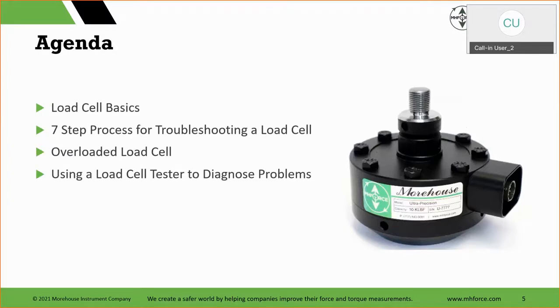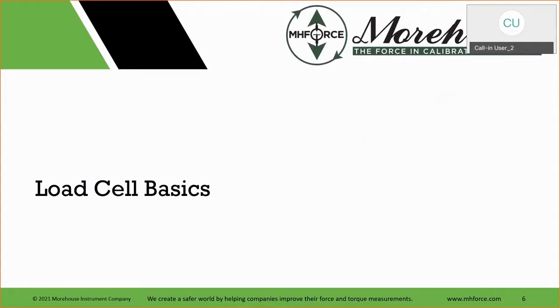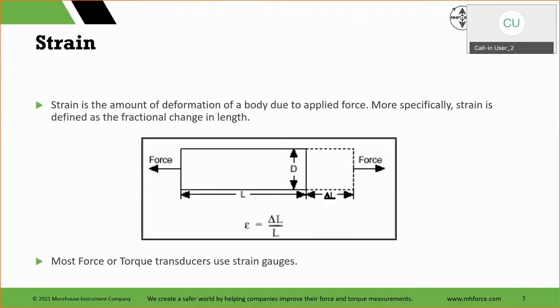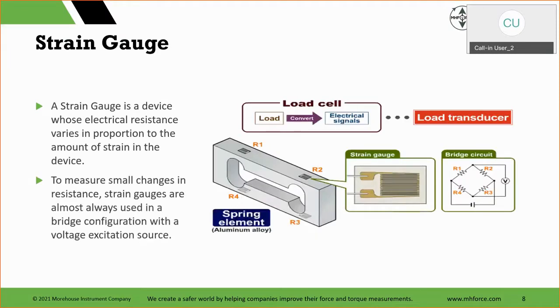So the agenda is load cell basics, 7-step process for troubleshooting a load cell, overloaded load cell, and using a load cell tester to diagnose problems. So basics of a load cell. When we talk about load cells, we're often measuring strain, and that's the amount of deformation of a body due to applied force. More specifically, strain is defined as the fractional change in length. And almost all force and torque transducers use these things called strain gauges. And when laid properly and done right, that allows you to put forces or torques on the various cells, and that sensing component will output typically a millivolt. Most of them output a millivolt.